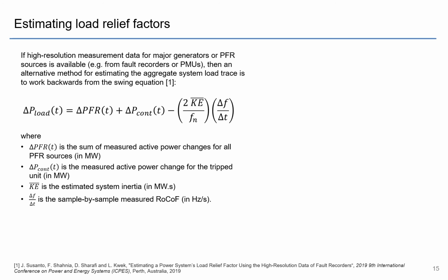If there was high resolution measurement data available for the major generators or the PFR sources in the system, from fault recorders or PMUs, then there's an alternative method for estimating the aggregate system load rather than just taking readings from the SCADA trace. That's to work backwards from the swing equation. If you had all the PFR source traces, you could get the aggregate change in PFR. You've got the trace for the tripped unit, so you can get the change in power of the tripped unit. You have an estimate for inertia, and you have the sample by sample rate of change of frequency estimate. You're filling in the blanks of the swing equation, and whatever's left over is your load.